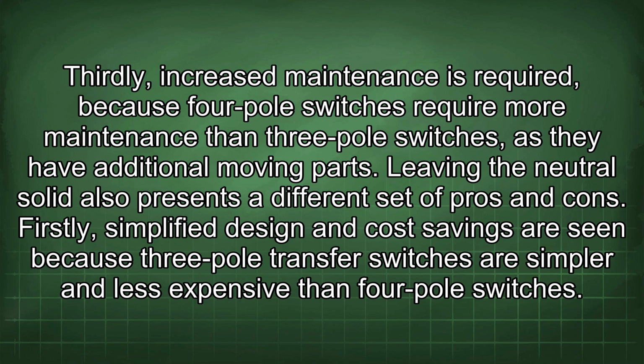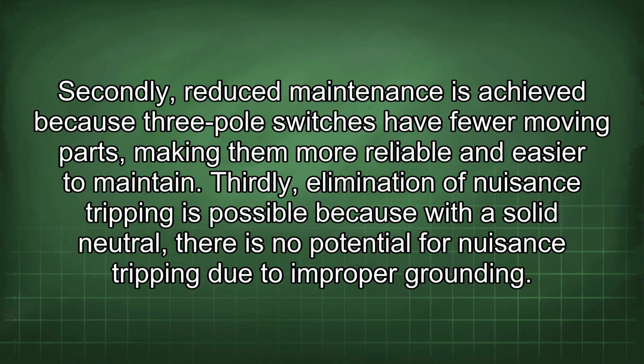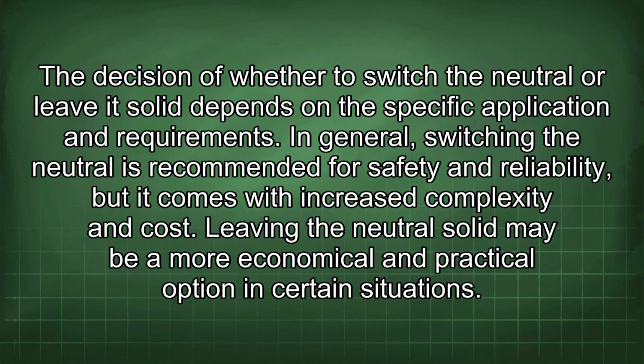Firstly, simplified design and cost savings are seen because 3-pole transfer switches are simpler and less expensive than 4-pole switches. Secondly, reduced maintenance is achieved because 3-pole switches have fewer moving parts, making them more reliable and easier to maintain. Thirdly, elimination of nuisance tripping is possible because with this solid neutral, there is no potential for nuisance tripping due to improper grounding.